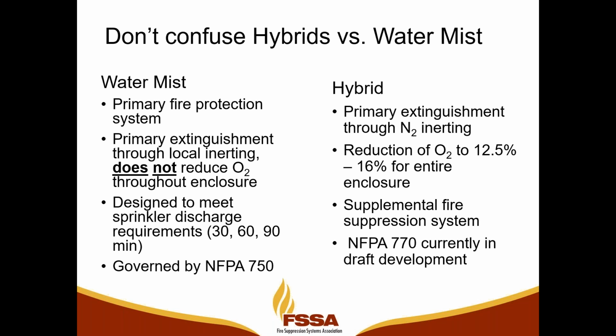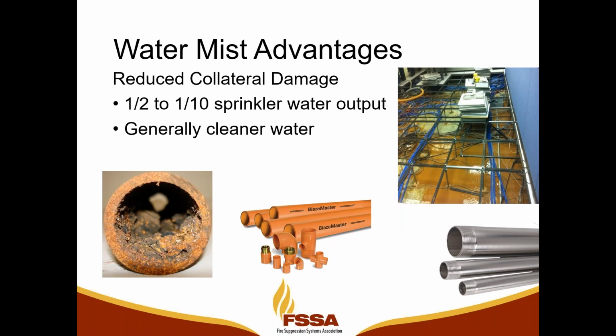That can be the only system that has to be installed. From a hybrid perspective, if you're going into a data center or something to that effect, this would be a supplemental system that would have to have a sprinkler backup installed, mainly for life safety purposes. So those are some of the differences between hybrids and water mist. We all see a confusion in the marketplace between the two, so we wanted to point out the differences between what a water mist system is and what a hybrid system is. And with that, I'll turn this over to Jason, who will go through the second half of the presentation. Thanks, Jonathan.